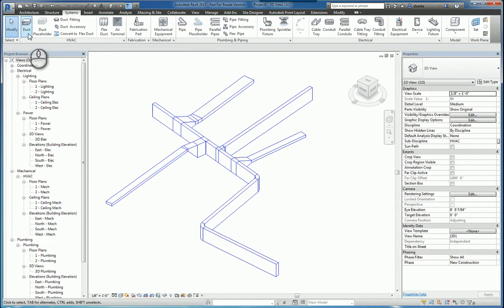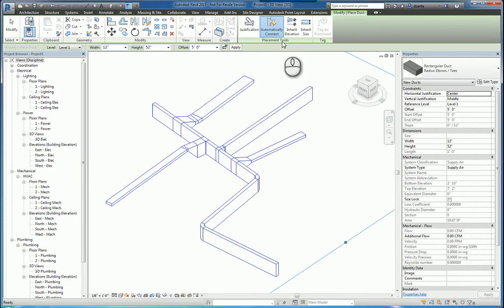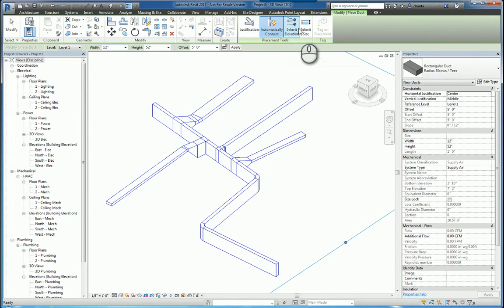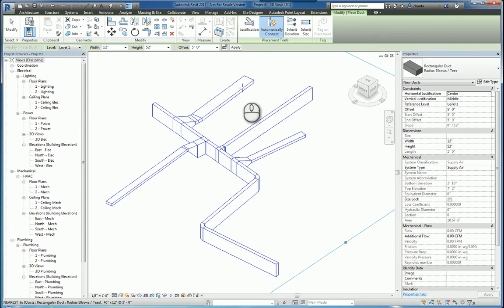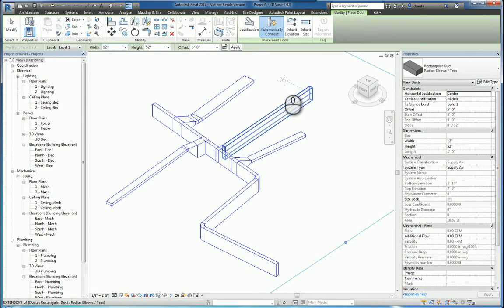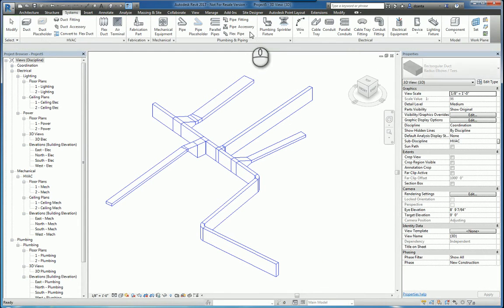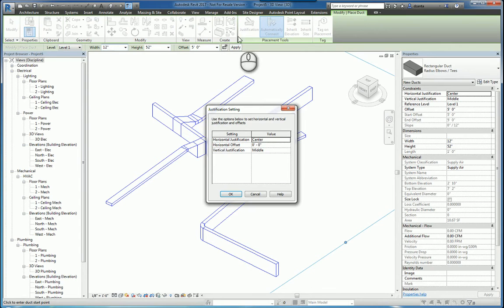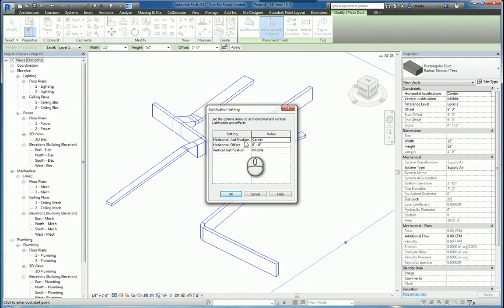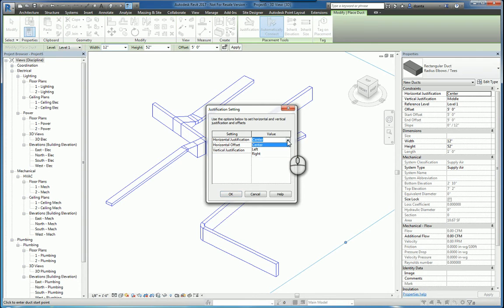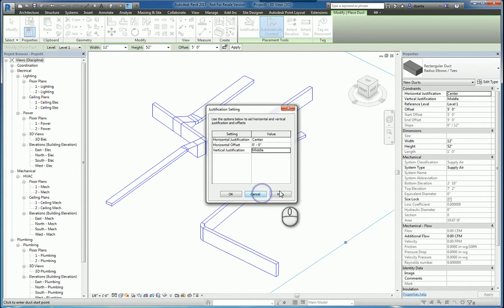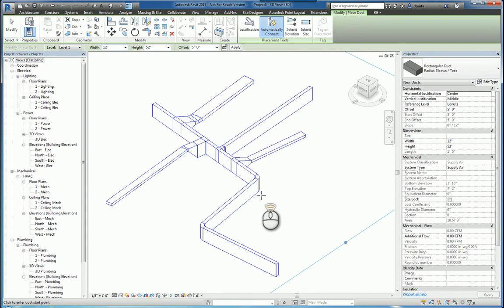So those are the contextual placement tools commands within Revit. These apply to ductwork, cable tray, conduit, and piping. And then lastly, I forgot to mention, the justification feature allows you to specify how the objects are going to be justified. And the default is centered. But you can say center, left, or right, and any horizontal offset if you need to, as well as the vertical adjustment being middle, bottom, or top. Thank you very much for watching.